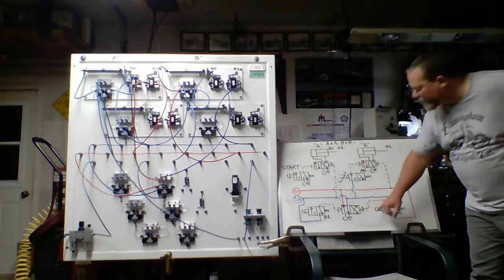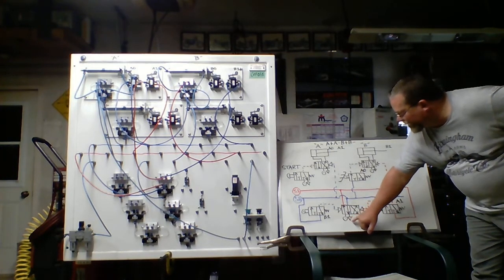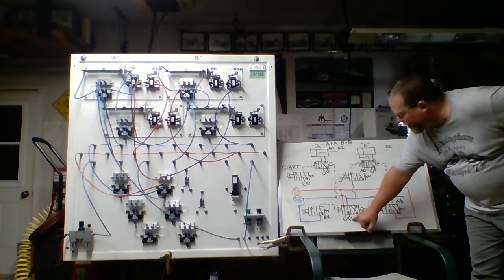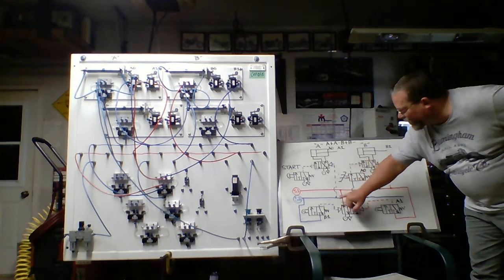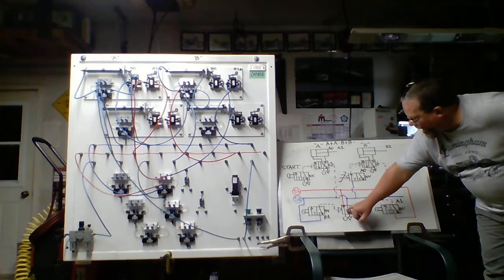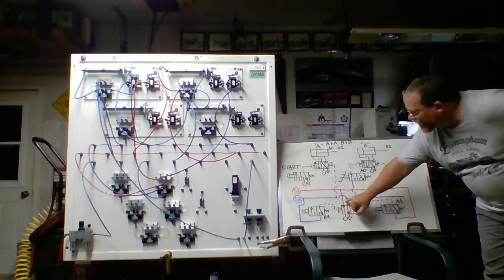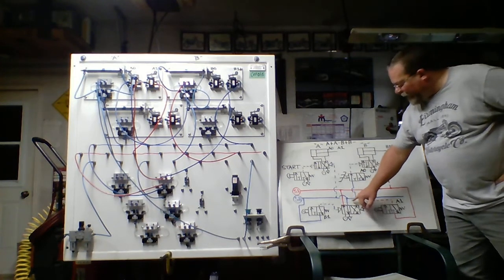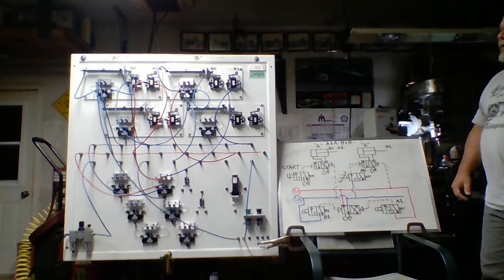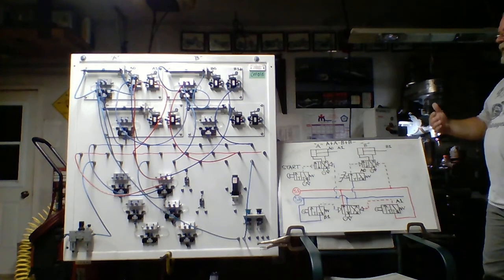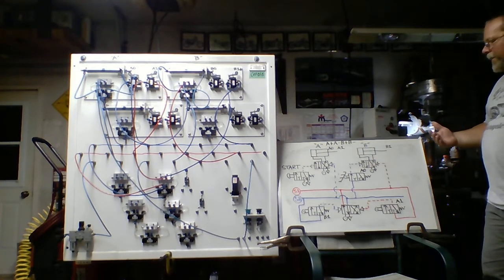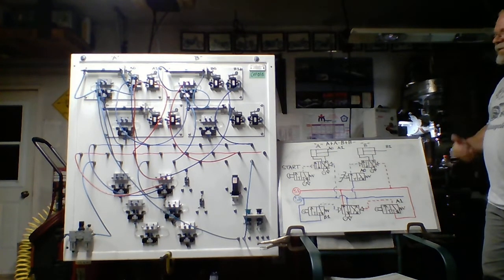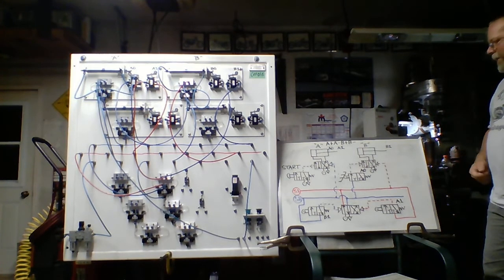So going back in to the cascade valve, again, we're taking the main source. As shown here, here's my exhaust atmosphere. And I've colored in red source 1, colored in blue source 2. So right now, when you look at the flow path of your 4-2, source 1 is energized. And we have to shift this cascade valve in order to get source 2 to become energized. The idea of this, of course, is neither one has air pressure present at that time. So it's either one or the other. And, of course, this will eliminate any conflict within the circuit or within its design.